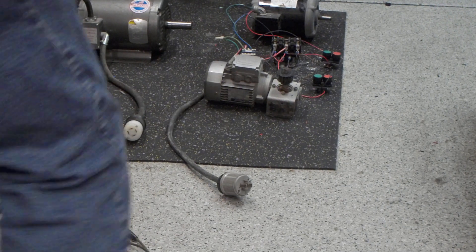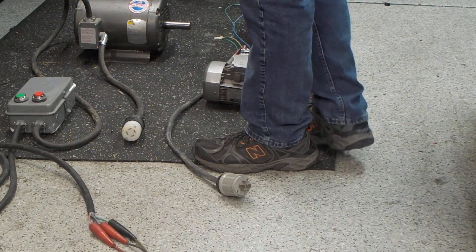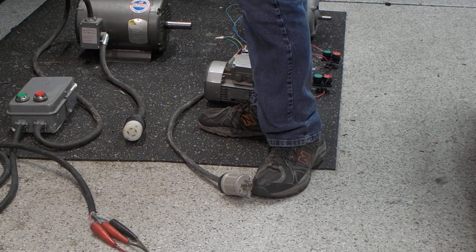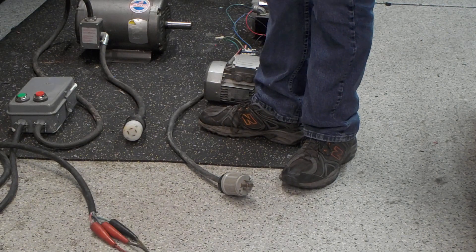Aloha, I'm Mike. What we got going on here is this is a Baldor M3218T. It's a 5 horsepower, 184T frame NEMA motor. It's supposed to be pulling about 14 amps at 230 volts. It's 1,725 RPMs. This is a three-phase motor.